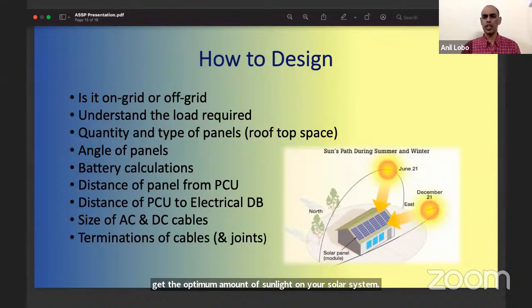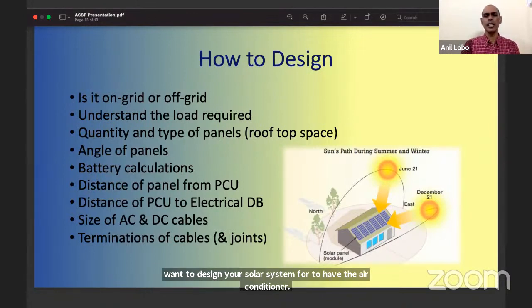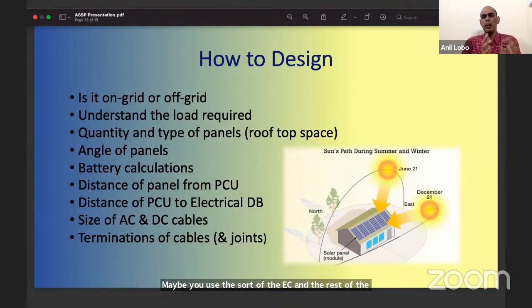The next thing is your battery calculation. Ask yourself how much battery backup you need and how big your battery load will be. For example, if you only use air conditioners for 3 months a year, around April, May and June, do you want to design your system around that load, especially if you use the AC for just 1 or 2 hours the rest of the year? In that case, you can have a smaller battery and run the AC on the grid instead. But things like your washing machine, microwave, induction cooker, water pump, fans, lights, TV, and computers running on battery, even at night, need to be factored into your battery calculation.